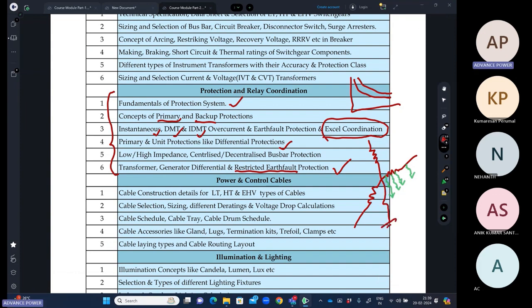types of grounding system in a transformer, it will be solid grounded or resistance grounded. These fault current parameters will change accordingly. So we will discuss in very much detail those parameters and how we do the settings for that.